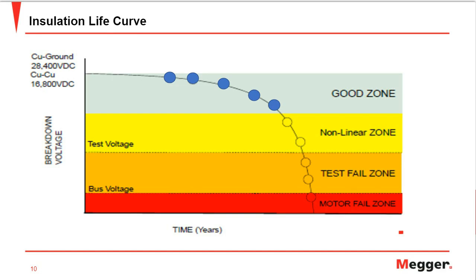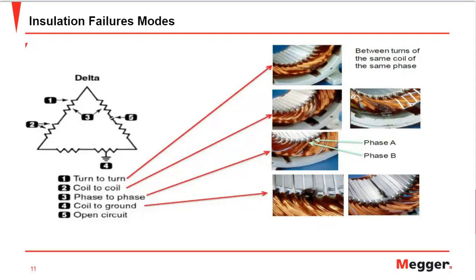Moving ahead, let's look at the insulation failure modes in a motor. The first one is the turn-to-turn failure mode, which is a major failure mode. It comprises at least 80% of electrical stator failures. 80% of those begin as a turn-to-turn fault, which then transforms into coil-to-coil, and then eventually phase-to-phase, and it goes into progression. So it's very important to determine if the motor is having a turn-to-turn fault. And the only test which we use to determine a turn-to-turn fault is surge testing, which we'll cover in the upcoming slides, with all the details about surge testing.